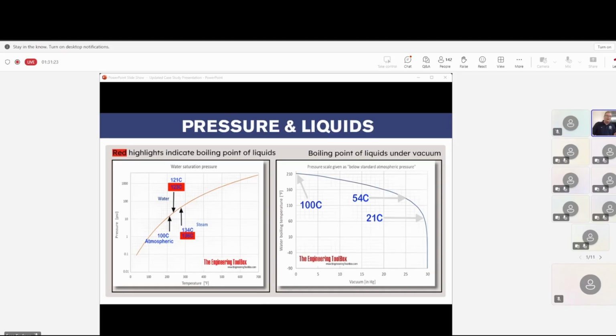So if you're adding water to your bag because you want to create steam, you have a little bit of a problem. So you go, okay, Bob, you know what I'll do? The autoclave can crank up to 134 or 274 degrees. So we're just going to crank up the heat and we'll get that water to boil. A little bit of a problem here. At 134, that equates to 32 psi in the autoclave. So you're running 32 psi, and at 32 psi, your water boiling temperature is 136. It's actually 135.6. I rounded it up.